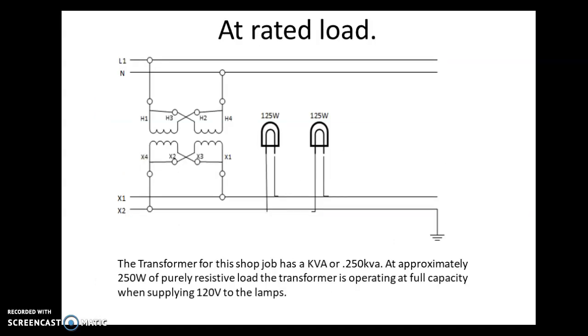At rated load for the second voltage reading of this shop job, we'll have the transformer loaded up with 2 lamps at 125 watts apiece, which will give us approximately 250 watts of power being drawn out of the secondary side of the transformer. With the rated load being 0.250 kVA, our current draw will be approximately that of which will put the transformer at its fully rated kVA capacity.